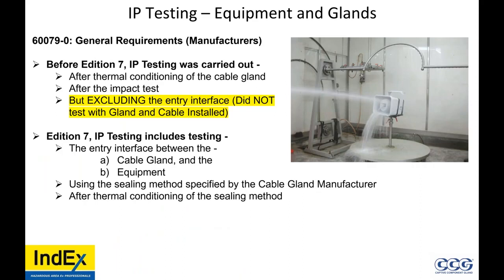Now, testing of equipment and glands. We call it the entry interface. Before the 7th edition of this standard, IP testing was carried out after thermal conditioning of the gland and after impact testing, but excluding the entry interface. So this picture shows you a test that would not meet the current requirements, edition 7. There's no cable and no entry device entering that device during this IP66 testing. This test means nothing. It is not sufficient. It would not meet requirements.